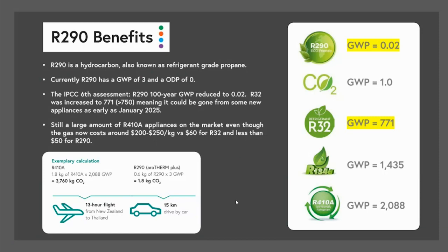The only refrigerants that affect the ozone are chlorofluorocarbons, a lot of which have been regulated out of the industry already. You might remember back 10 or 15 years ago, there were a lot of propellants and hairsprays and things like that being banned because they were fluorocarbons and they were creating a very damaging effect on the ozone layer. These refrigerants don't really have any of that problem, but the global warming potential is a different story. That's to do with the greenhouse gas effect.